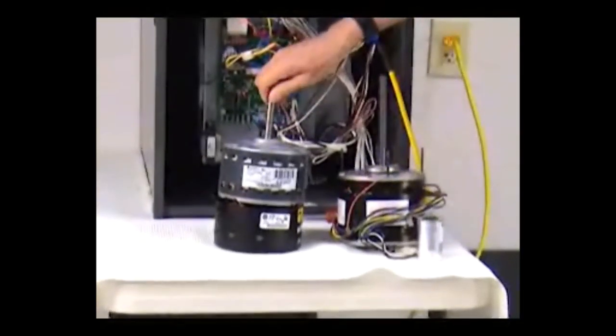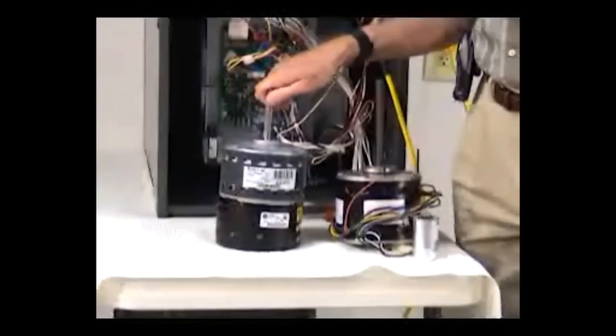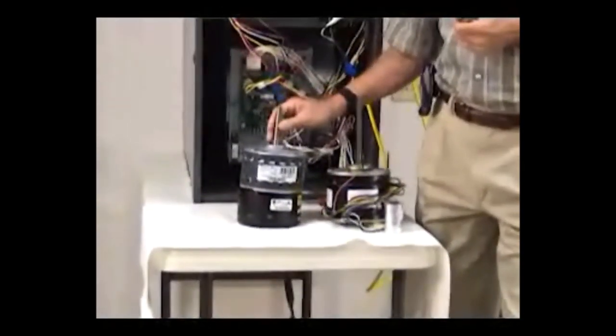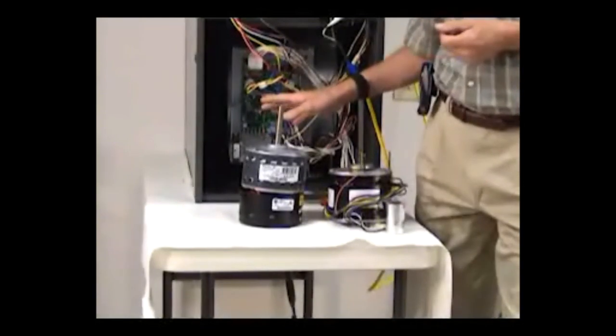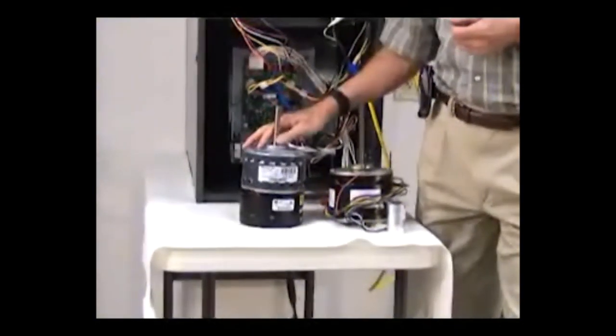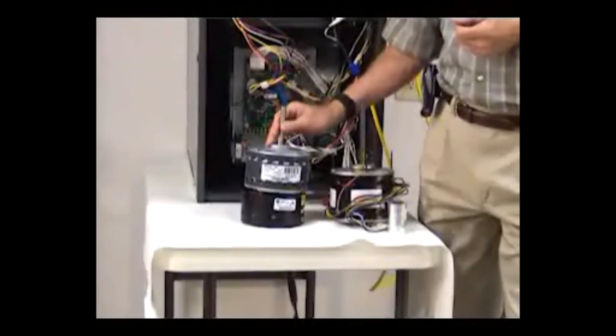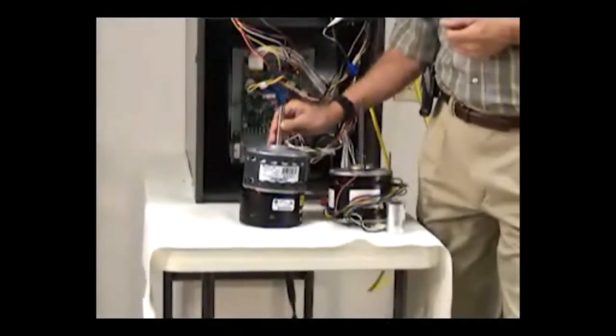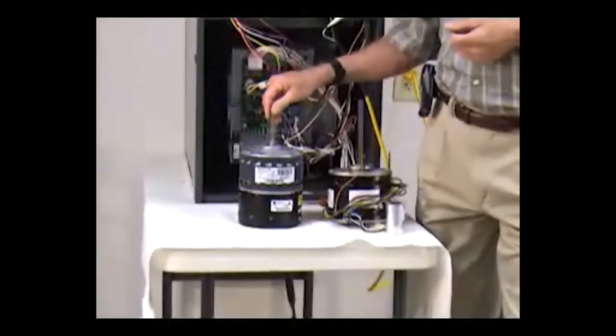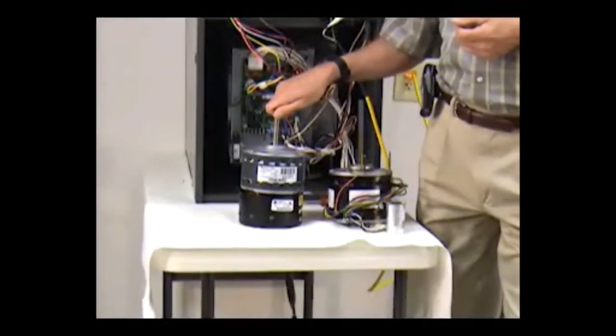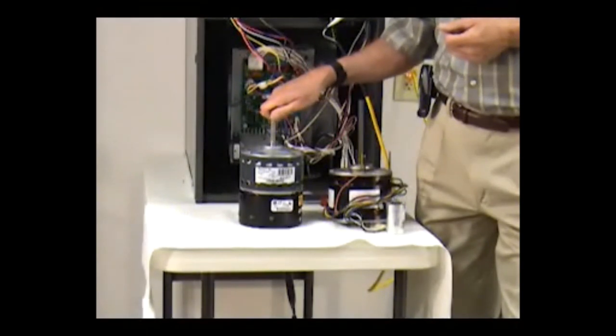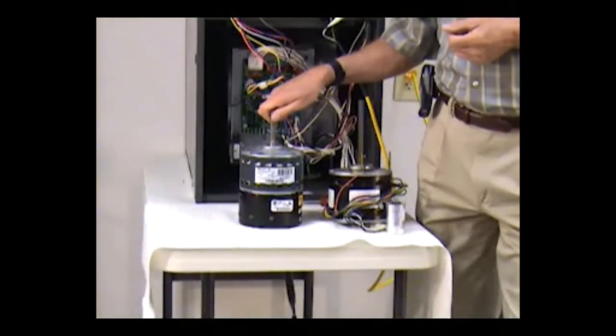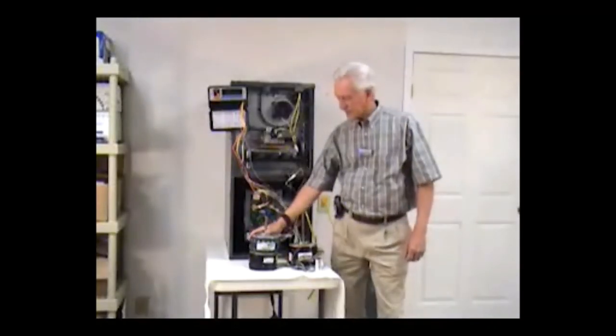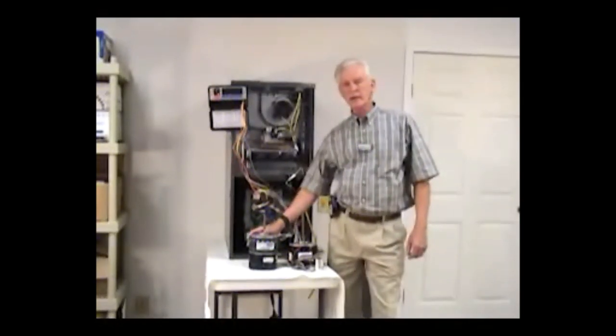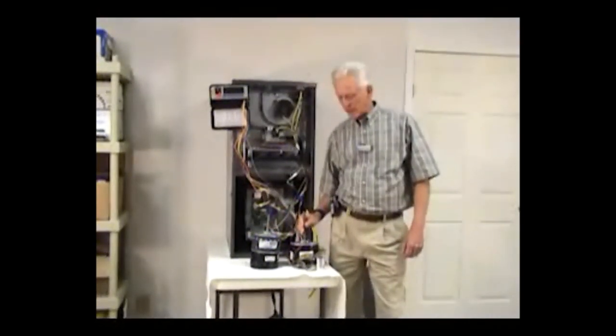They're even using the ECM motors for condensing fan motors in higher SEER units. So we'll find them in air handlers, we'll find them in gas furnaces, we will find the ECM motors in condensing units. So we're going to have to start looking at what we need to do to be able to service these motors. Also, very important that we find out how we need to service the units and keep them operating properly. To make the comparison to the ECM motor now, and where it differs from the split capacitor motor.